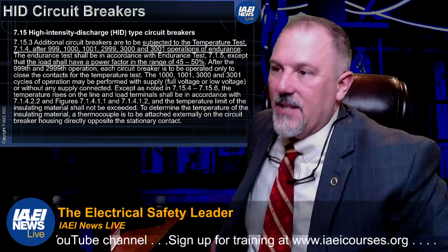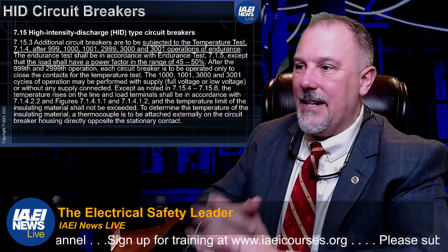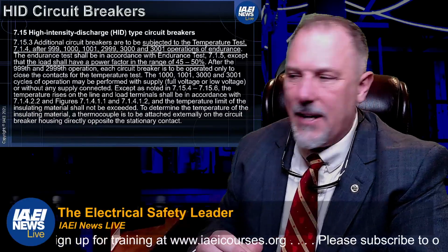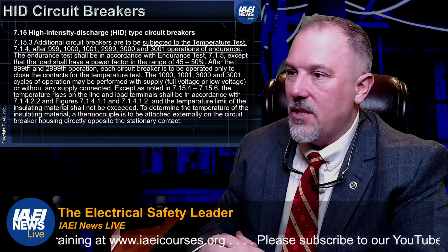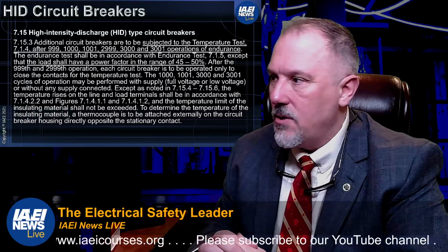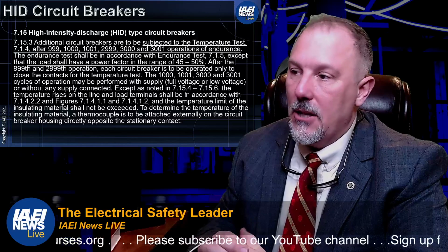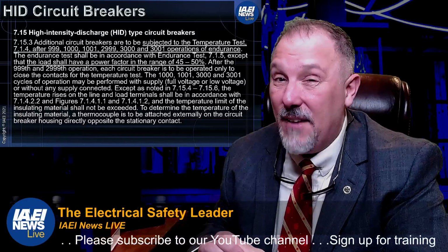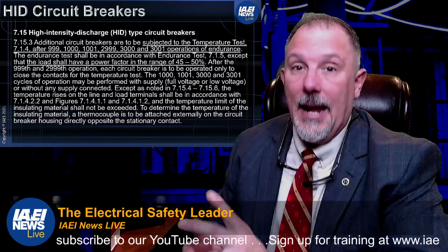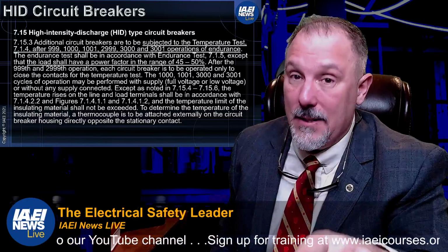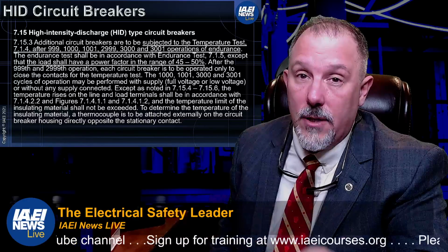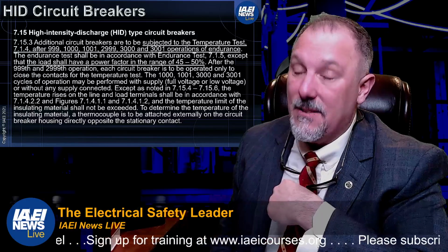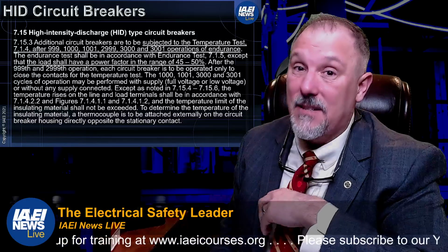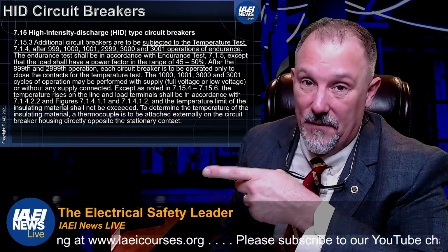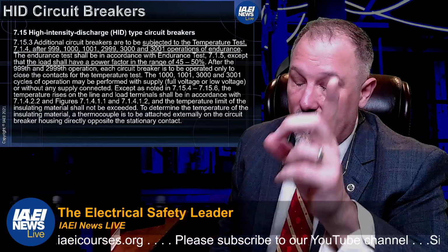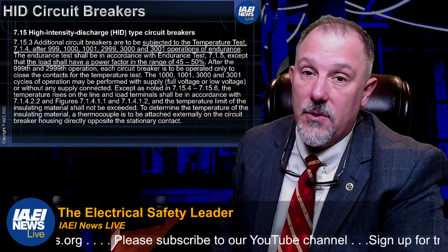Subject to temperature tests after 1,000, 2,000, 3,000, etc. operations of endurance. The endurance test shall be in accordance with endurance test 7.1.5, except that the load shall have a power factor in the range of 45 to 50%. And you might say, boy, that's unrealistic, but I'll tell you what. Go out there and look at manufacturers' information, and my gut tells me that the least expensive ones are in the 45 to 50% range. Compact fluorescents, some of those can be at 50%.